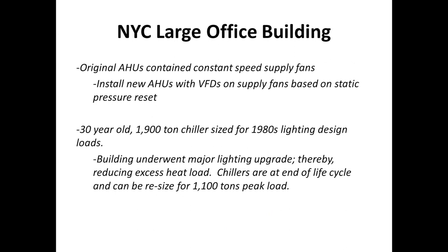The original air handling units had constant speed supply fans. So there were VAV boxes in each space. These VAV boxes, as they closed, just built up pressure in the supply duct, and the supply fan was just forced to ride its curve. There was no VFD to ramp down the speed of that fan. So this building had to install new air handling units, since the old ones were about 30 years old anyway.